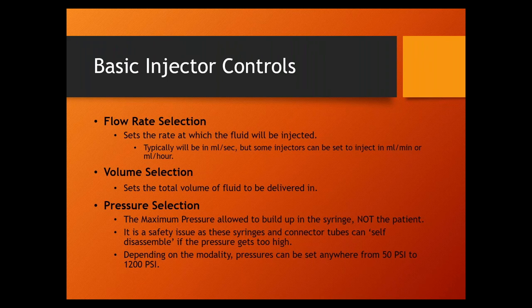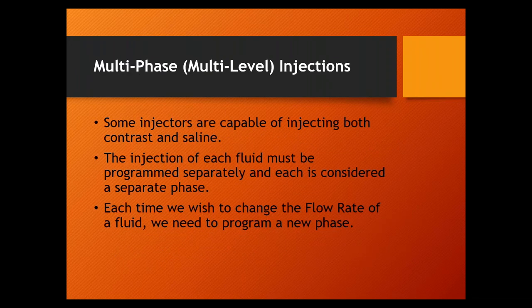Injection of each fluid must be programmed separately as a separate phase. Each time you wish to change the flow rate of a fluid, you need to program a new phase. Sometimes phase one and phase two might both be contrast - phase one with a faster flow rate to fill the body part quickly, then phase two switching to a slower flow rate to continue with the remainder of the injection.